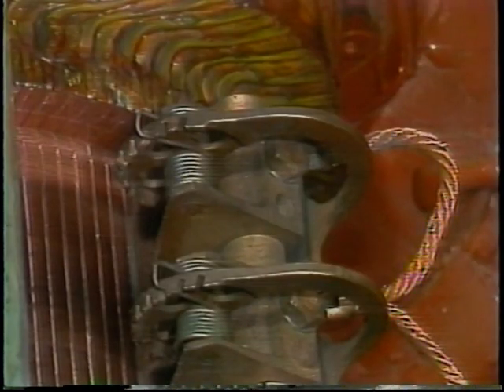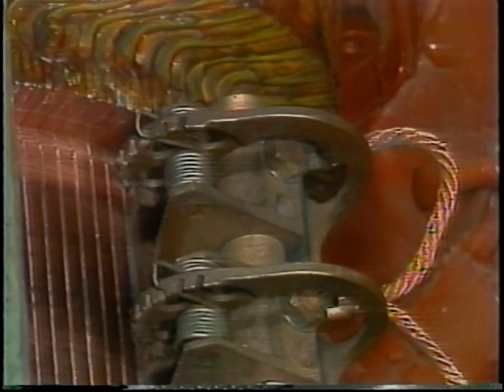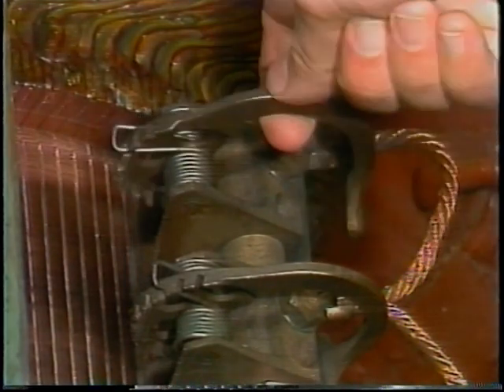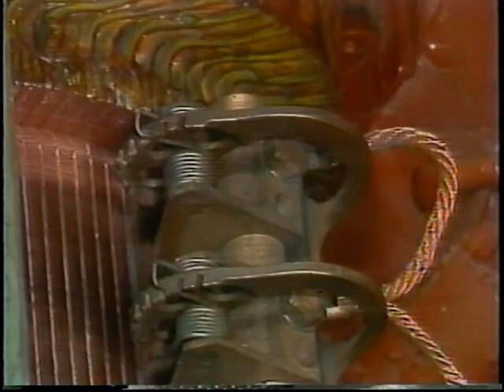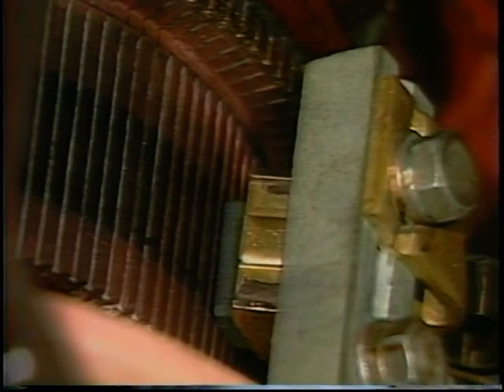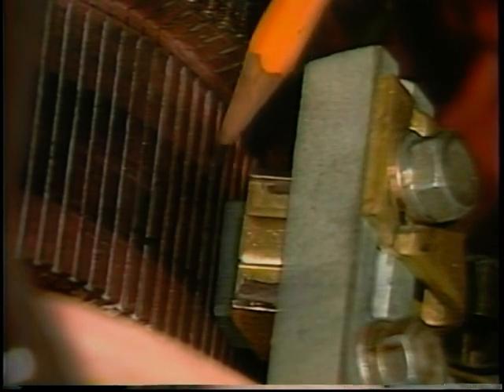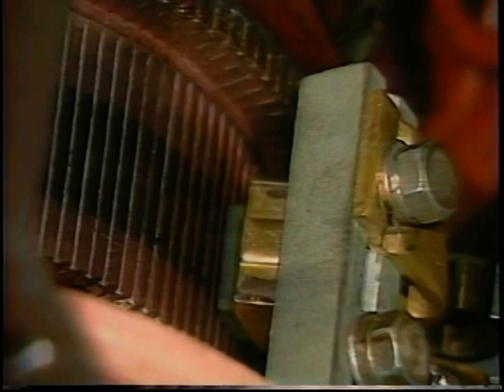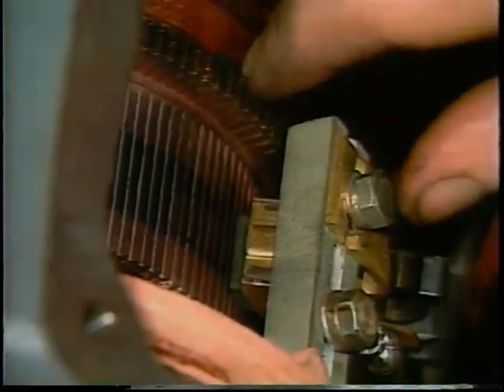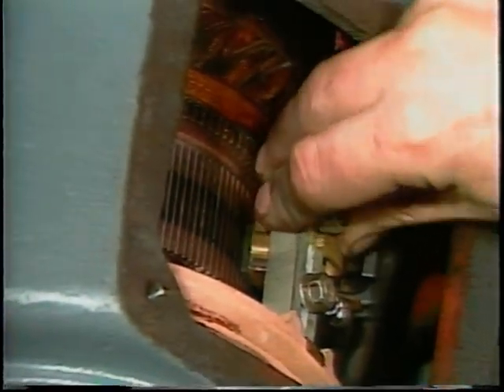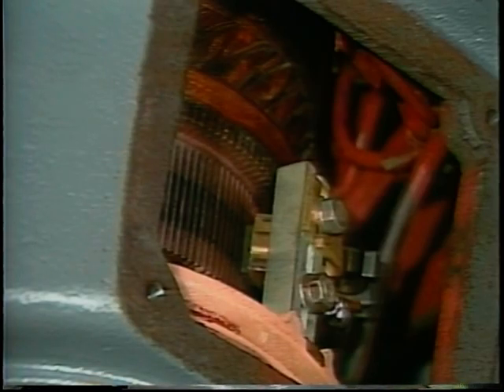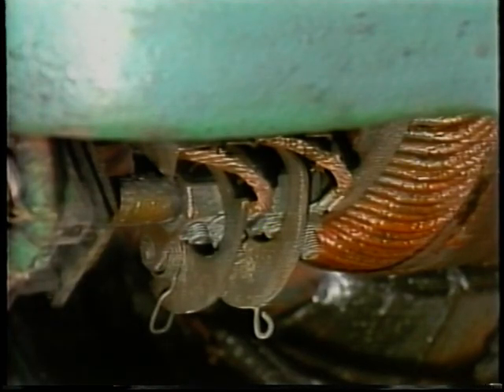The brush rigging, including the brush holders and the springs which press the brushes against the commutator, must be in good shape. The brush holder should be squarely aligned so that the long dimension of the brush is exactly parallel to the commutator bar. Any looseness or misalignment of the brush holder around the commutator will cause problems. Even if the brushes appear to be operating properly, check brush length and condition.